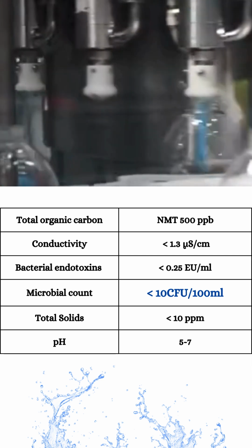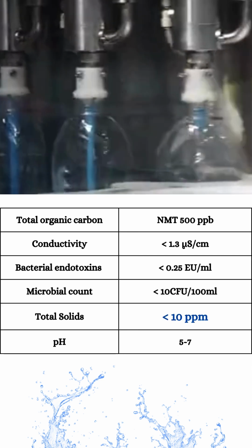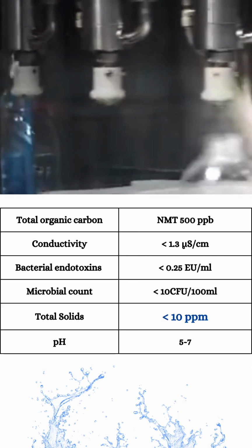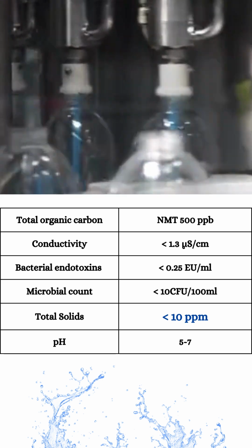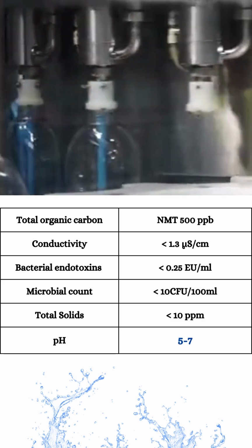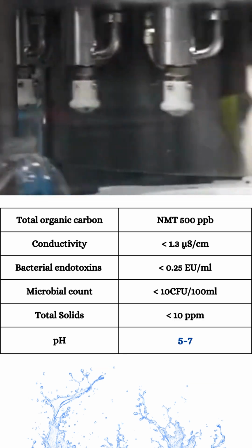The total aerobic microbial count must be less than 10 colony-forming units per 100 ml. The total solids must be less than 10 parts per million. The pH range should be between 5 to 7.